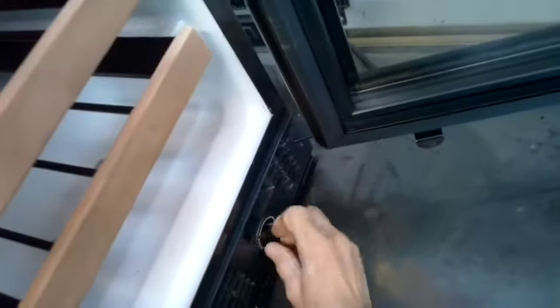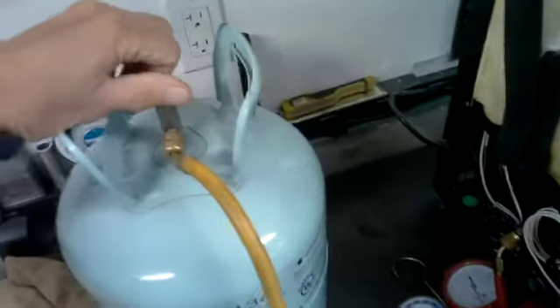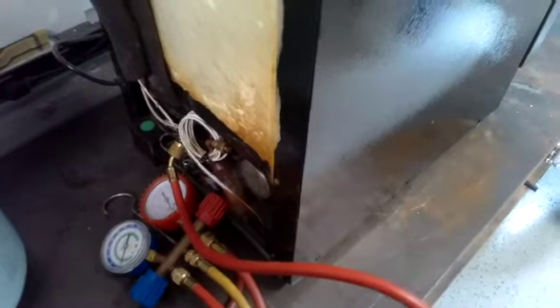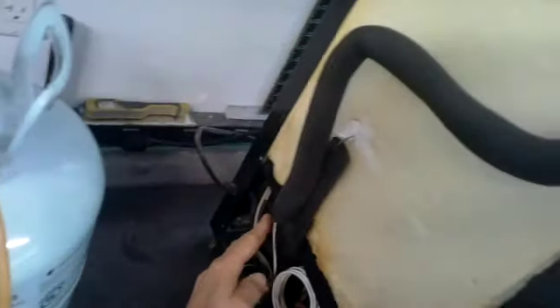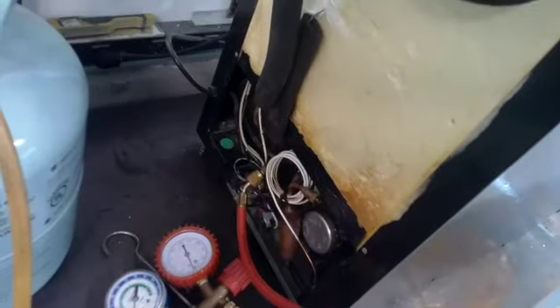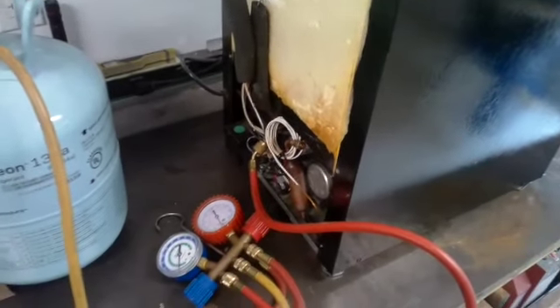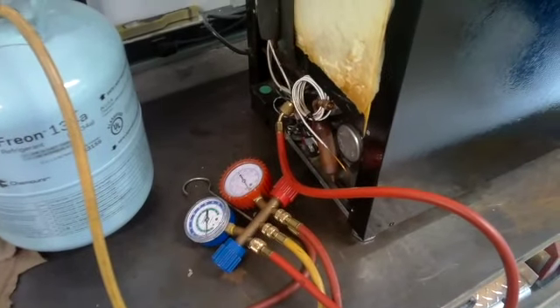So we turn it on. It's now on. We'll keep an eye on the temperature and let it run. We'll open up our tank and start to recharge it, and then we'll watch our suction line and do a superheat test on it or a frost back. Now there's a cover here that goes on the back that will also add some insulation, and it covers the whole compressor area and everything. So once we figure out that it's working properly and secure that, we can button this up and call it a day. Anyway, we'll get back as soon as we confirm that everything's okay.